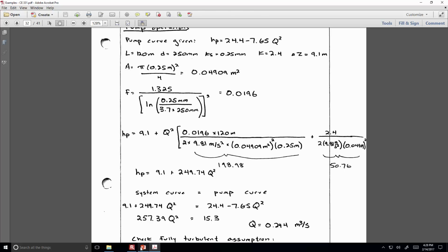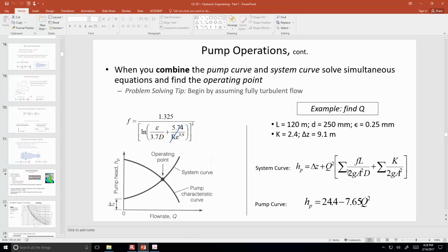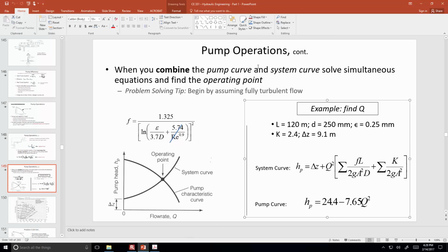I had a good question as I was wandering around. Somebody said, when does the sum come into play here for the system curve? In our case, you just had one L and you just had one K. But if you had multiple pipe segments that were a different diameter, for example, then you'd need to calculate each of those segments separately. Because here in the denominator, you're having A squared times D. So you just have to take each segment that had a different pipe diameter and treat it on its own. And then combine them together.